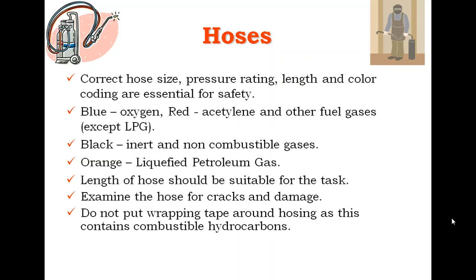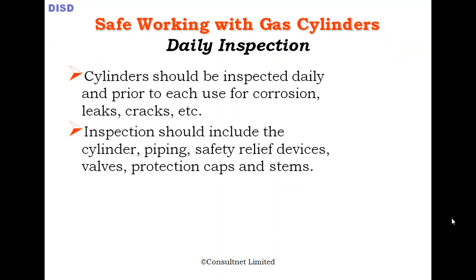For the daily inspection checklist: cylinders should be inspected daily and prior to use for corrosion damage, leaks, and cracks. The inspection should include the cylinder body, pressure relief device, valve protection caps, and fittings. Regulators, cylinder valves, and other equipment should be taken out of service if they are damaged — including damaged regulators or hoses.